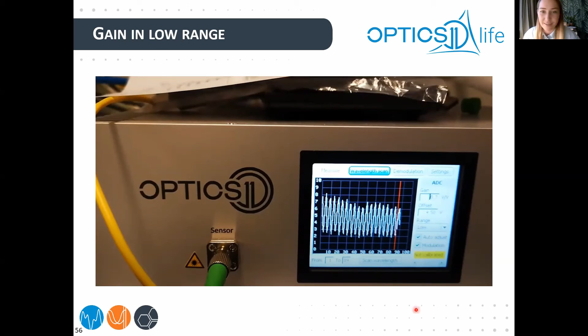Now the next step is to find the surface. We can find surface from the calibration window, and this find surface should end up in contact with the stiff sample, so with the glass slide, for example, or glass petri dish. Actually, you need to make sure that this glass petri dish is clean, and also that the probe is clean, because that will influence, as I will show later.